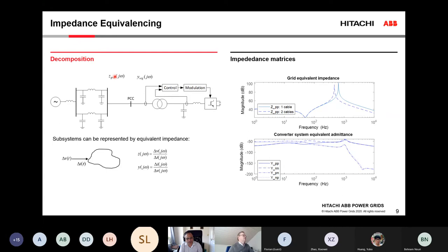For the converter system, we typically use, say, a model-based approach. So we actually build the converter, so we know in detail the data of the different components. So, for example, for a transformer, we can measure in the lab and do component validation component by component, and then aggregate all those components here. I think one research topic here that is more or less an open field is this validation of the grid impedances, because we do have models, but we don't really know how accurate they are. So if you go beyond, say, 2.5 kilohertz or 5 kilohertz, it starts getting very tricky. And what you need to do then is make sure we have some level of conservativeness.